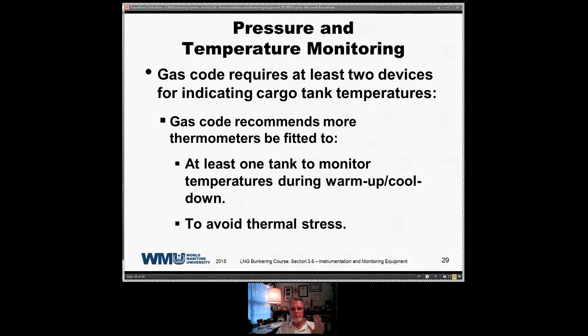So as you go along through these procedures, you're monitoring your temperatures, and if you begin to get any deviations and variations that you don't expect, you may have a problem, and now you have to investigate what's going on. Why isn't this temperature coming down? Or why is this temperature coming down too quickly? So not only are you concerned about something lagging, but you're also concerned about something that may be progressing too quickly. If you see things like this, you can make the modifications in your system that are necessary in order to do it in the controlled manner that you want.